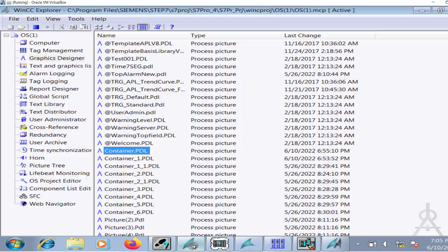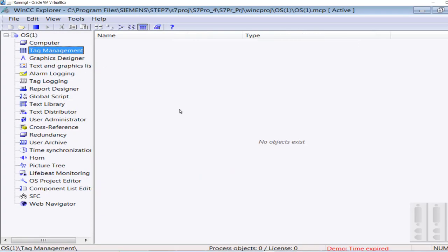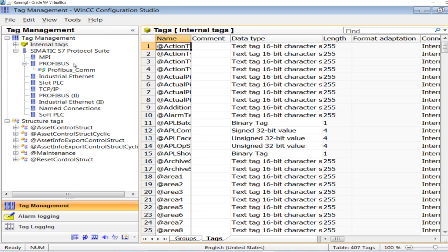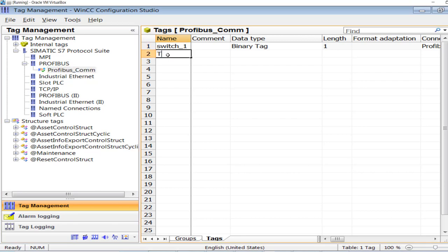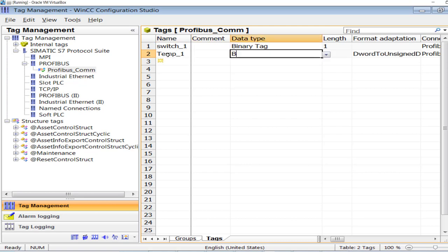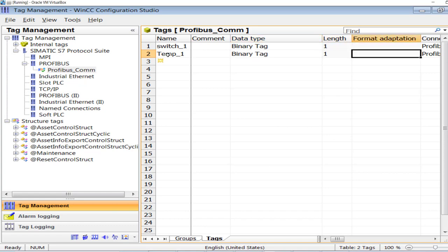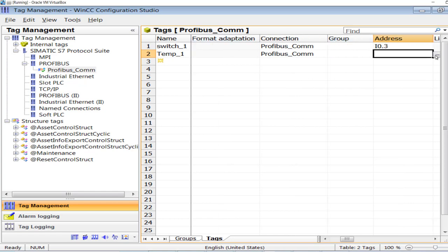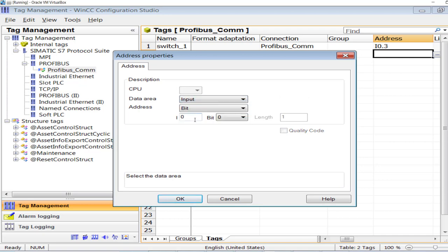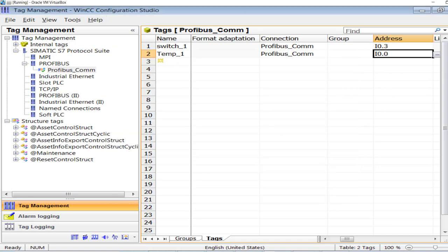Go to tag management. The communication between WinCC and PLC is Profibus and it is established. I will name the tag 'Temp1'. The data type of this signal is binary. The connection name is Profibus communication and the address is I0.0, input 0.0.